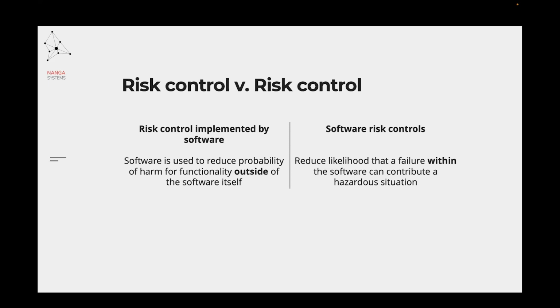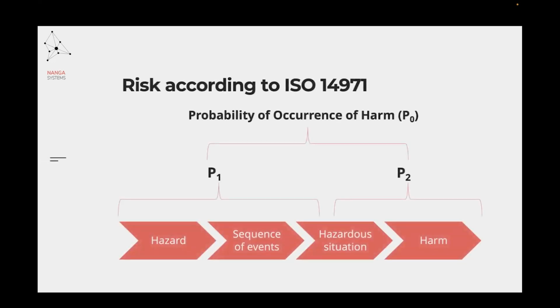And software risk controls, these mean that we reduce the likelihood that a failure within the software can contribute to a hazardous situation. And in this topic, risk management in case of software as a medical device development, we are focusing on software risk controls on the software system level. The determination of the probability of occurrence of harm according to ISO 14971 is something that we can perform with the help of P1 and P2 values, where P1 is the probability of the hazardous situation to occur, and P2 is the probability that it will lead to harm.